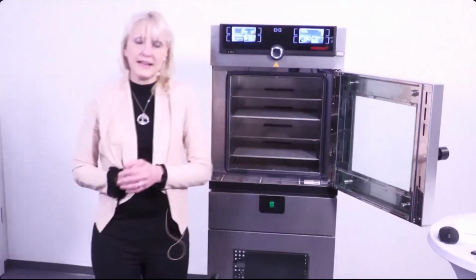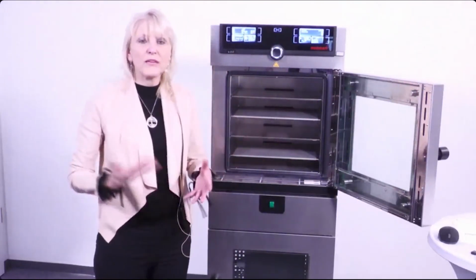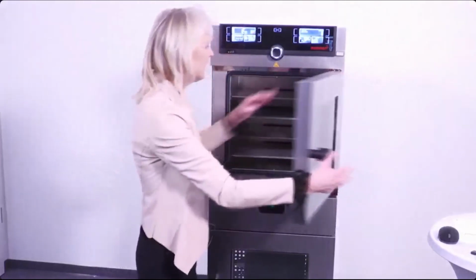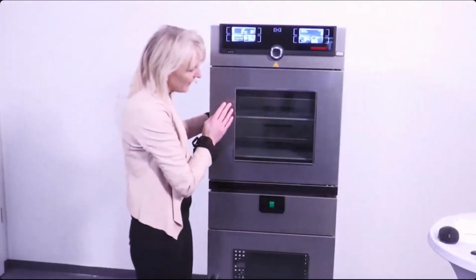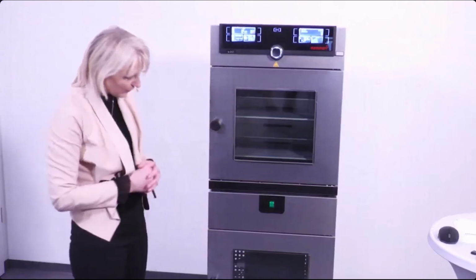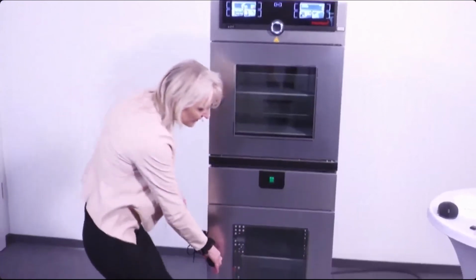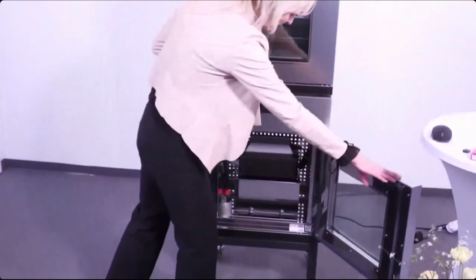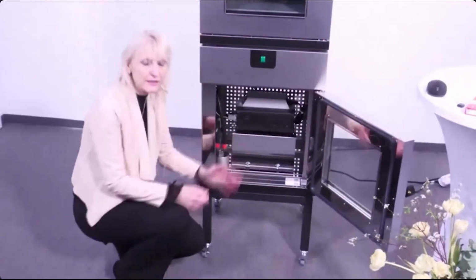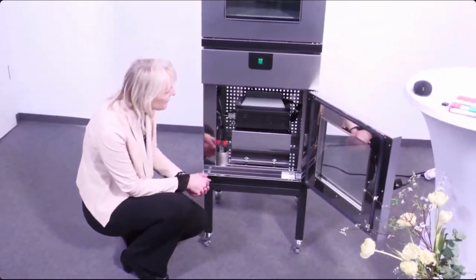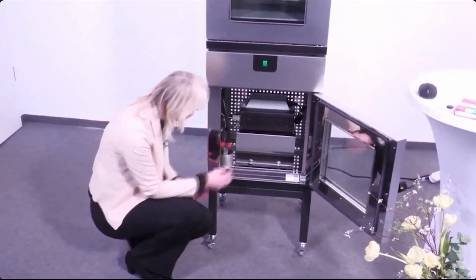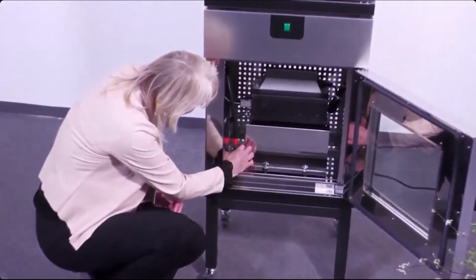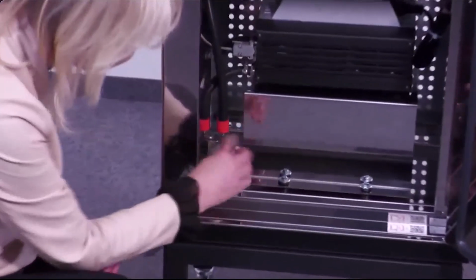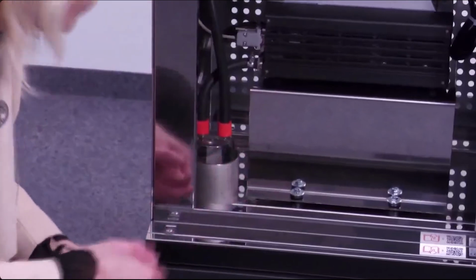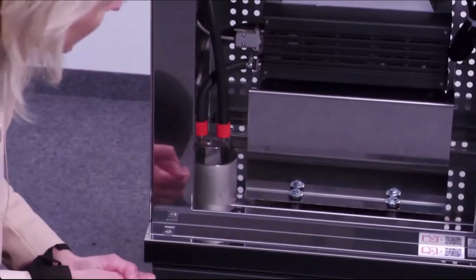All, of course, is stainless steel, and because there's more pressure, we even use here a higher grade of stainless steel for the interior chamber and for the tubings. Then let's have a look at this pump. That is a housing of the pump module. We open it, this one. Then we have here a chemical resistant pump, brushless, speed controlled. And we have here the condensed, let's say, vessel. So here the condensed water will be collected and it can be taken out and can also be emptied.